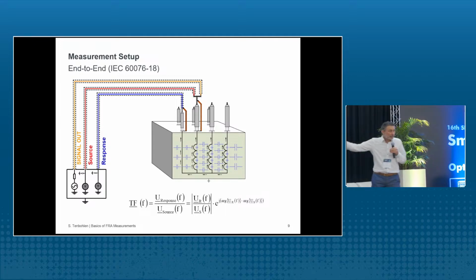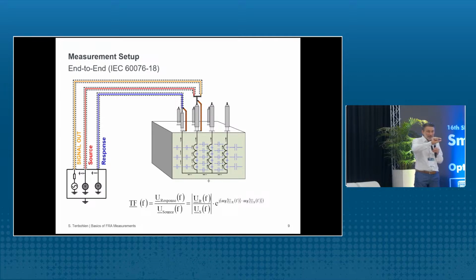Yeah, and you know, a bushing is a quite long thing. Yeah, so if you know an oscilloscope, you have there the BNC connector, and this BNC connector has in the middle the voltage signal, and the outer part is the ground connection, the shield of the cable. Yeah, but a transformer does not have a BNC connector. The ground is here at the tank. Therefore, you have to use the grounding strap to bring the ground to the measuring cables, because the measuring cables, of course, are also shielded, and must be grounded.